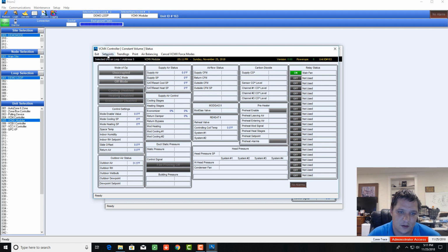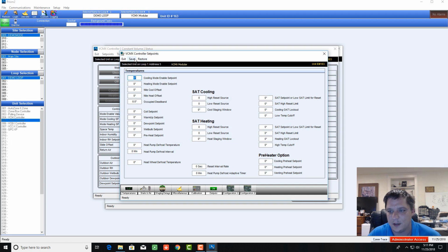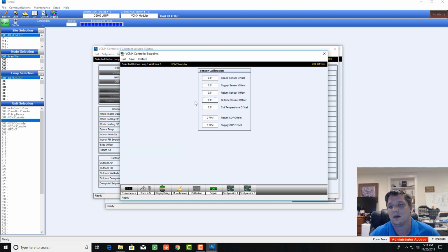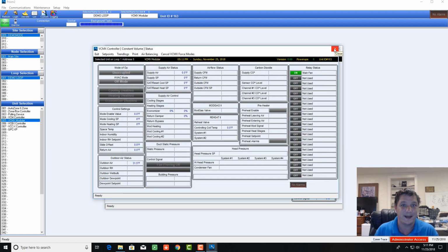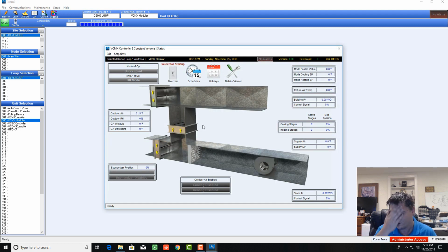But one thing I would definitely do is go ahead and save the set points in this set points folder here. So if something does get out of craziness, I won't be responsible for breaking the AAON unit even further. But I would probably not do any of this. I would just use this as the tool. It would be the same thing as me putting my hoses on it, but now I don't have to. I'd see what everything's doing. It'll show you the pressures and saturation temperature, so you can tell if it's low on charge or not. Pretty cool software, though.